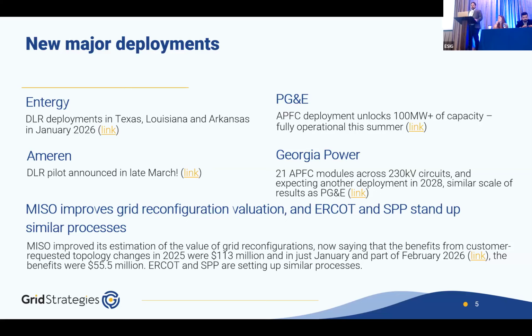Entergy, across Texas, Louisiana, and Arkansas, had the first multi-state deployment of dynamic line rating, though this was a pilot. Ameren also announced a pilot with DLR, deploying sensors on some of their most congested lines to get better real-time data. PG&E and Georgia Power have both recently deployed, or are in the process of deploying, advanced power flow controllers, unlocking around 100 megawatts of new capacity in each case to address load growth in their regions, and in Georgia Power's case, they expect to continue the deployment.